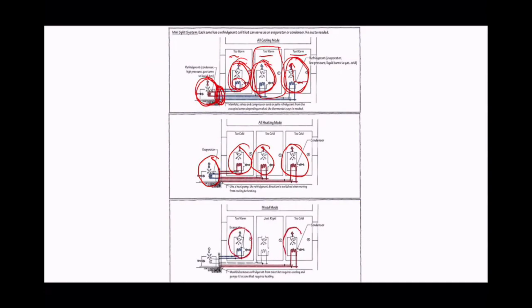We're going to have a situation where we can make one room hot, one room warmer, and one room colder at the same time. The advantage of that is severalfold. First, the advantage is thermal comfort, because we can provide cooling and heating at the same time. But the second advantage, if we have that mixed condition where we need something hot and something cold at the same time—this requires a little bit of a leap of faith, just trust me, the physics works out—we're moving heat from the too warm room to the too cold room.